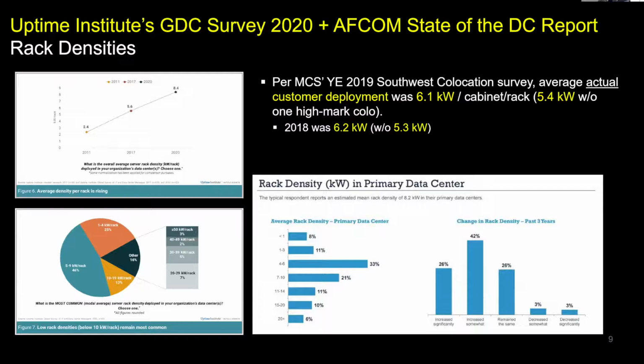One of the providers we surveyed typically has a pretty high mark. If you back theirs out, it's closer to 5 kW per cabinet. That lines up well with the AFCOM data center survey, where average density in 2020 was between 4 to 6 kW per cabinet. Now if you look at the Uptime Institute's survey, they say 44% are between 5 to 9 kW per cabinet. I'm less bullish on that survey because that's a pretty wide range. I think the sweet spot for corporate users is still right about 5 kW per cabinet. We'll hear what Cyxtera has to say during their presentation.